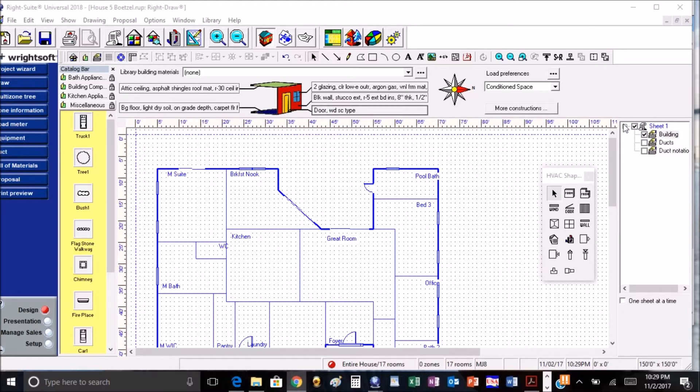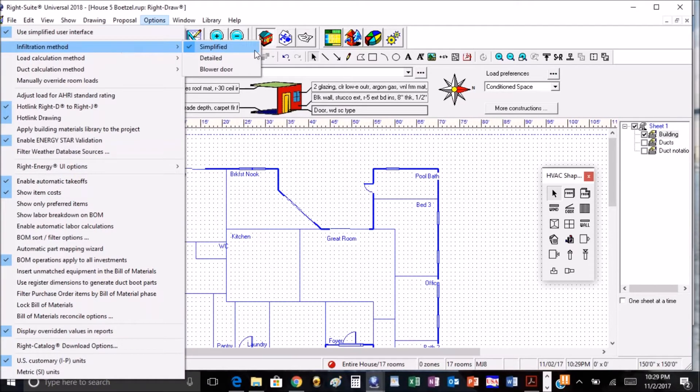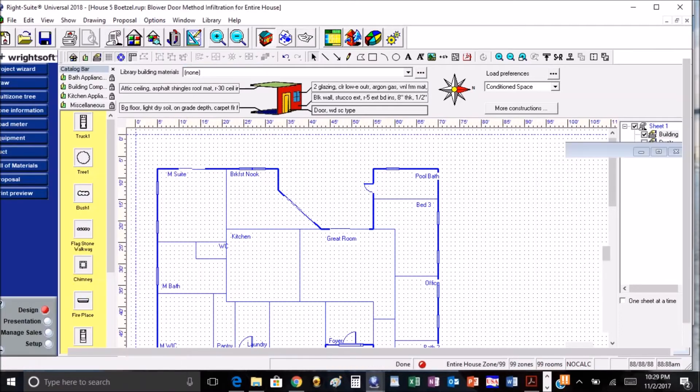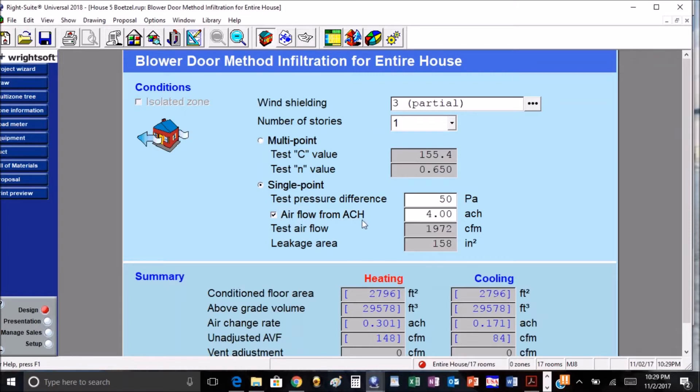One of the first things they have is we can set our ACH for infiltration in the blower door, which means that we can go up here to options, instead of using the simplified method we can go to blower door method, and then we can click on the airflow for ACH and we can manually type in what our ACH is.